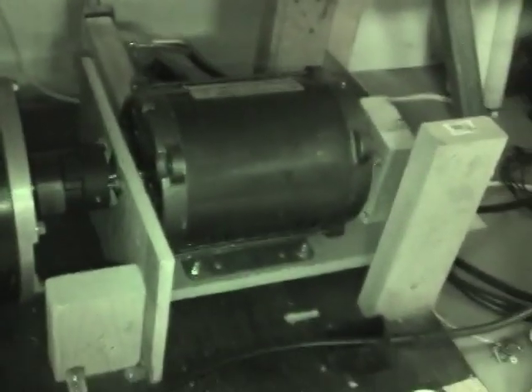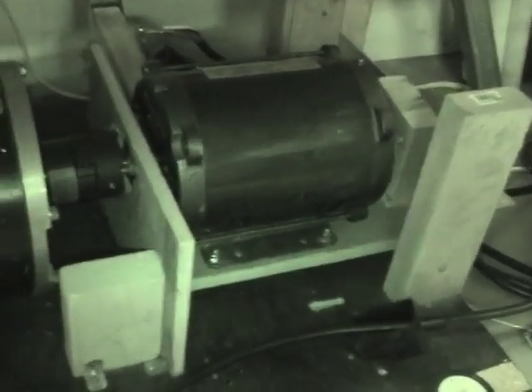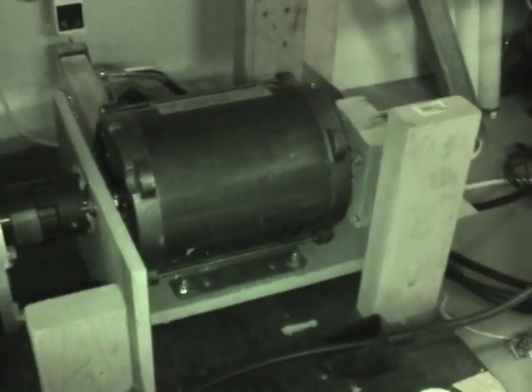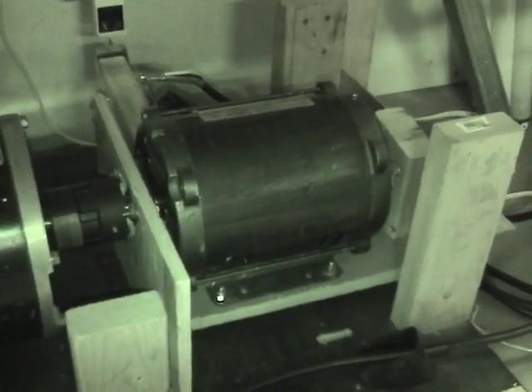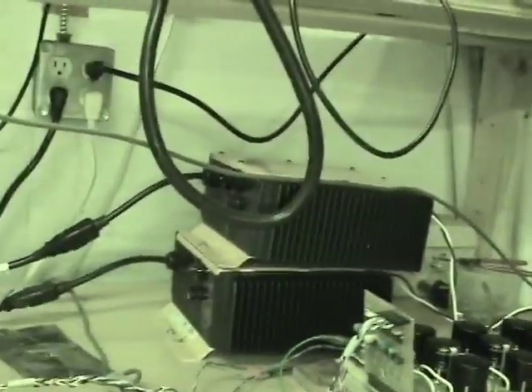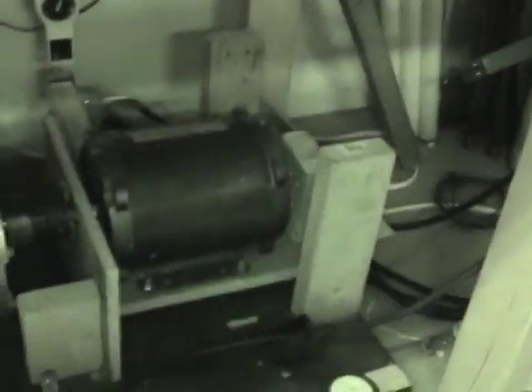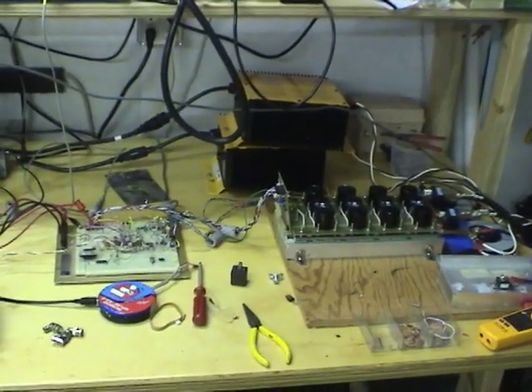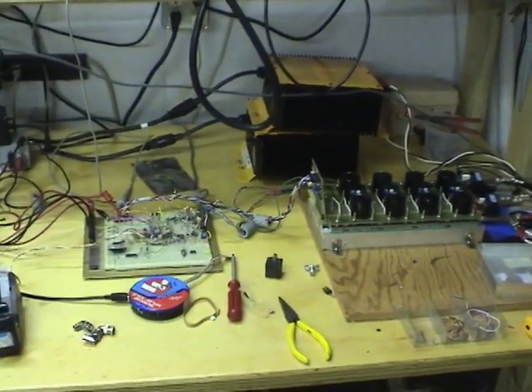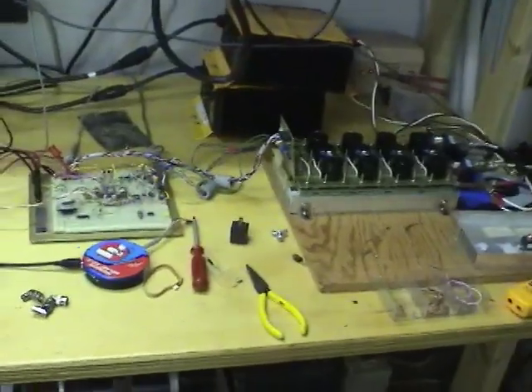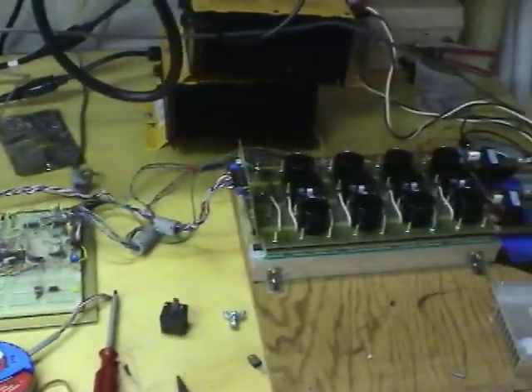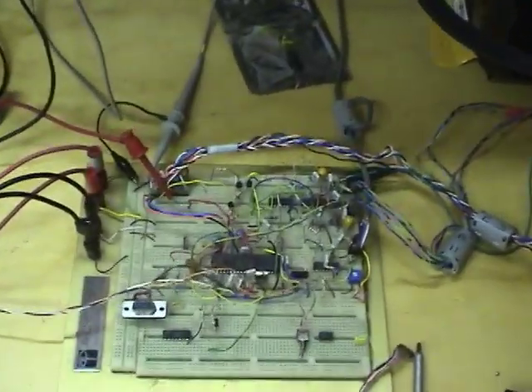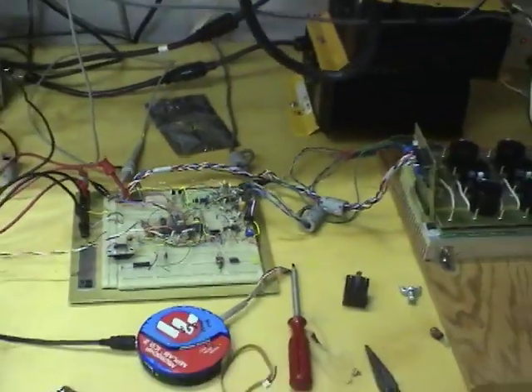The power supply gave out there, but about twenty-four foot-pounds, twenty-two and a half foot-pounds. And remember that this motor normally puts out about three foot-pounds. It's a one horsepower 1725 RPM motor, so that's about three foot-pounds nominal. So that's quite a bit of torque. And we're limited again by the power supplies. We can get even more torque if there's more power. I hope you found this video on the AC drive system interesting. If you want to know any more about it, if you want me to make another video or go into how vector control works in more detail, please let me know. Anyway, thanks for watching.